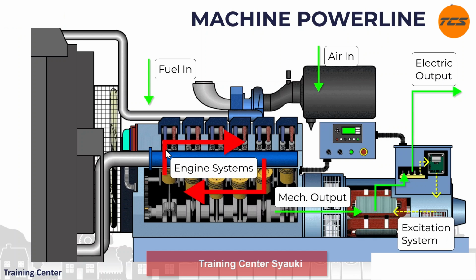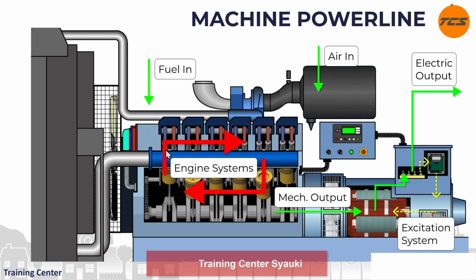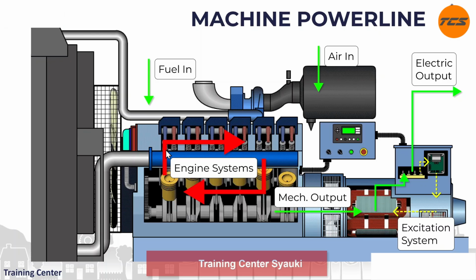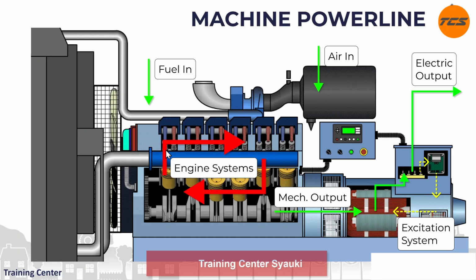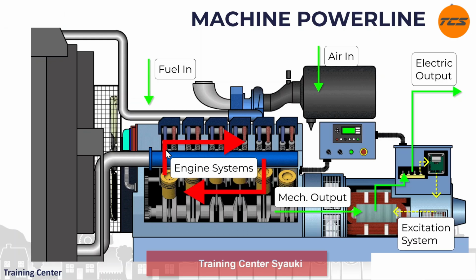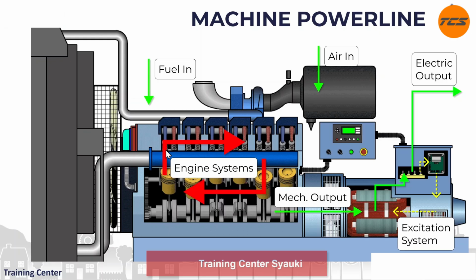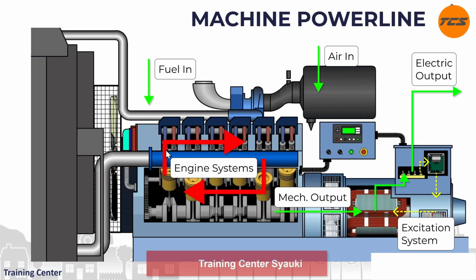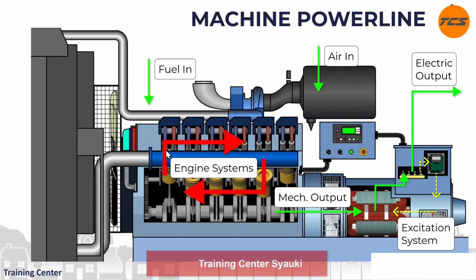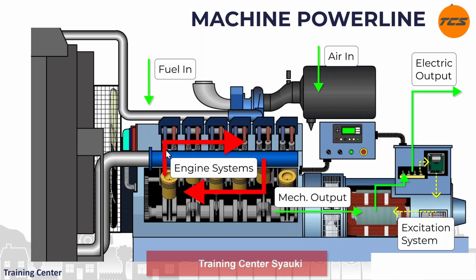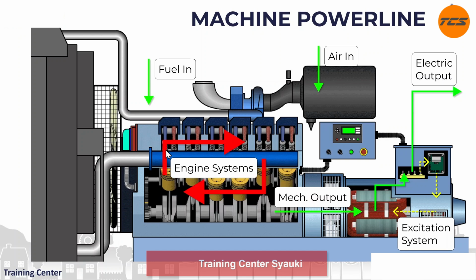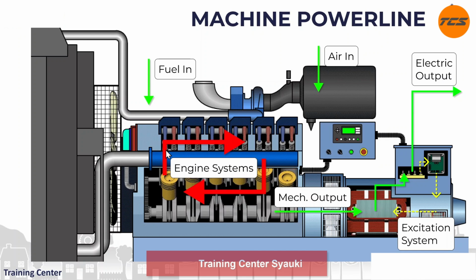In operation, the genset maintains a constant speed to produce a stable frequency, typically 50 Hz or 60 Hz, depending on the regional standard. When connected to a power line, a synchronization system may be used to match voltage, frequency, and phase sequence with the existing network to ensure safe and reliable power transfer. Protection systems such as circuit breakers and relays are essential to prevent damage from overload, short circuit, or abnormal operating condition.